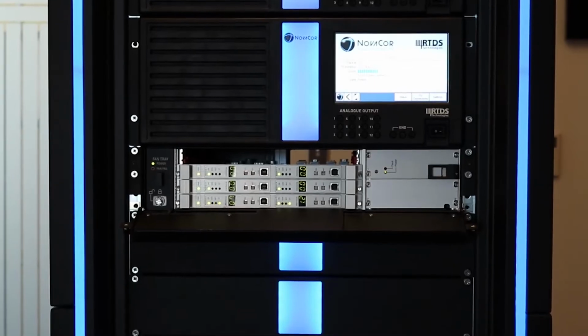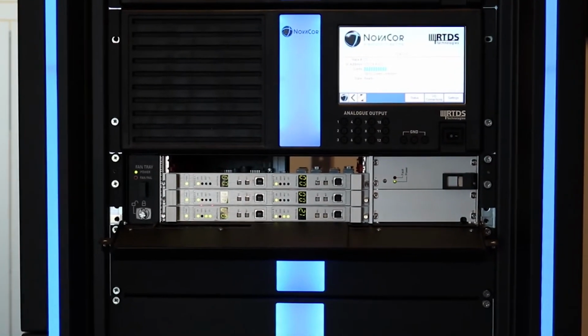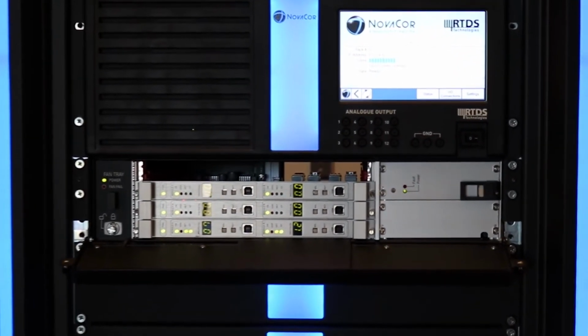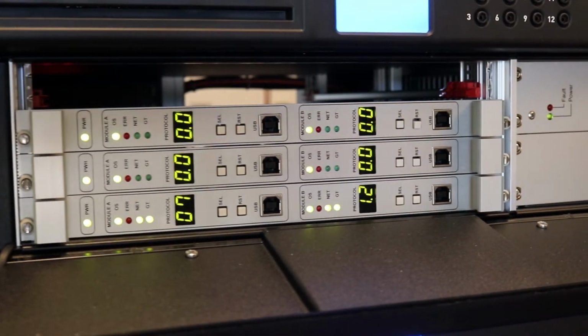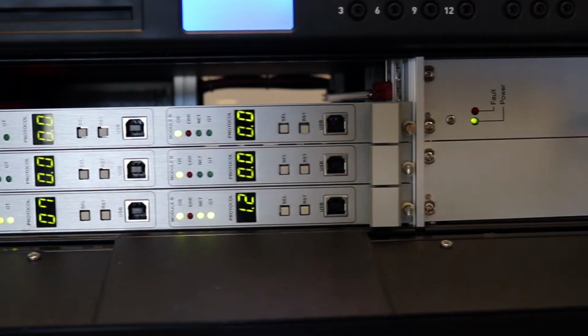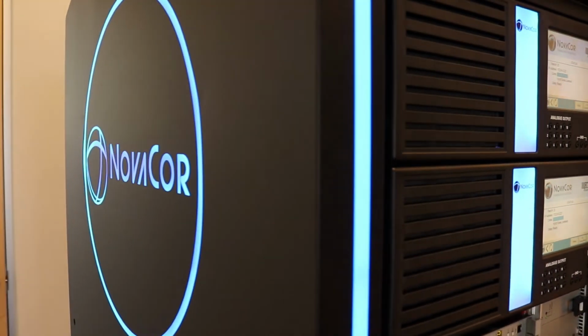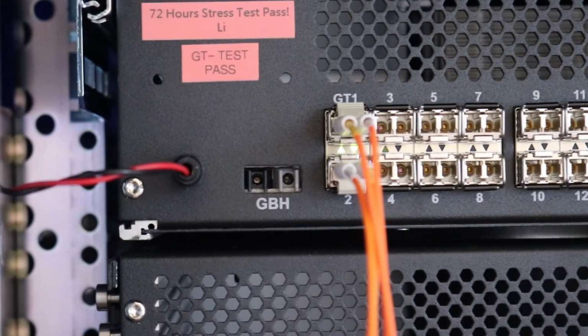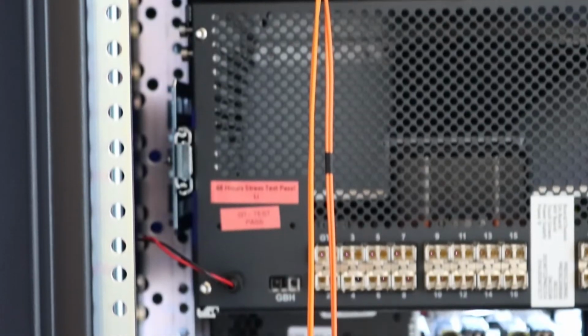The RTDS simulator's network interface card, called the GTNet, forms the interface between the simulation and the external controller. Signals are sent bidirectionally between the simulation and the GTNet via optical cable. The GTNet creates and reads data compliant with several different standard communication protocols and can be interfaced to multiple external devices via Ethernet.